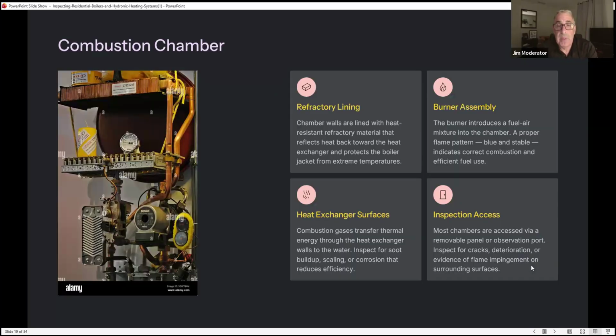Combustion chamber. So again, we put this into the PowerPoint just for informational purposes only. You're not going to be able to see most of the combustion chambers that you run across. So we have a refractory lining. Chamber walls are lined with heat-resistant refractory material that reflects heat back towards the heat exchanger and protects the boiler jacket from extreme temperatures. Burner assembly.